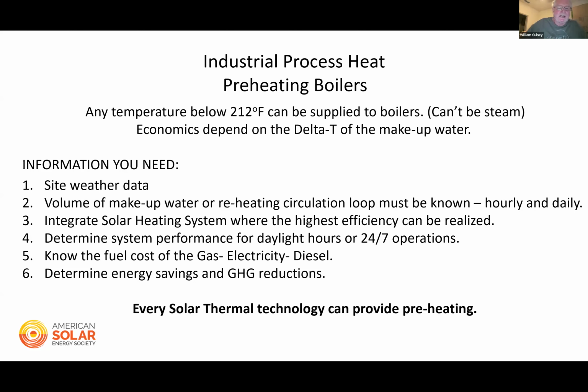So when we do a process heating survey, we need to look at what we can do. And we cannot send steam into a boiler. It has to be a liquid. So it's got to be below 212 degrees, which means it doesn't matter if you're a low temperature collector generating 105, 110 degrees, a mid-temperature collector providing 140, 160 degrees, whatever your operational limits are, those preheated boilers can see significant reductions in their energy consumption. So we need to look at where the best application would be.